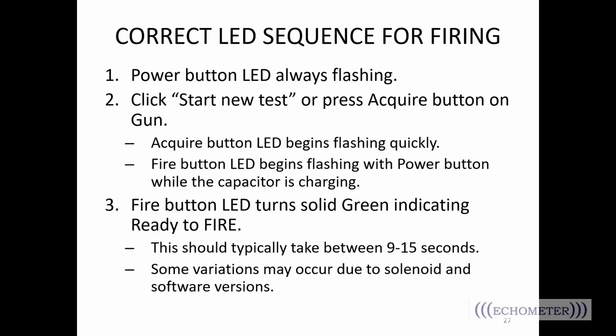All right, so when you fire your gun, your power button, of course, is always going to be flashing. You're going to click Start New Test, or you're going to press the Acquire button on the gun itself. The Acquire button LED light begins flashing quickly. The Fire button light flashes with the power button. And while that's flashing, the capacitor is charging. It's getting enough power to fire that solenoid.